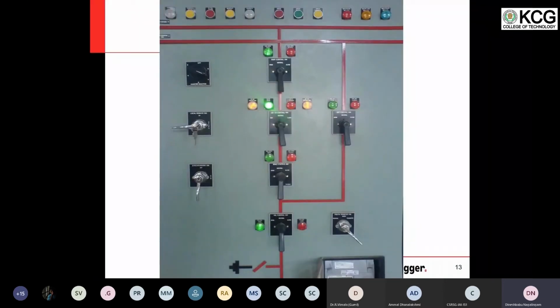Okay, a sample close-up look. You can see this green light is glowing. So green light glows means it's an indication that the breaker is open. So this is for breaker, and this is for isolator 89A and 89B. So I'm using some numbers like 89. This is nothing but the ANSI code. ANSI means American National Standard Institute. ANSI has given codes for all the equipments and protection system in power system. So if you Google ANSI, you will get all the details.